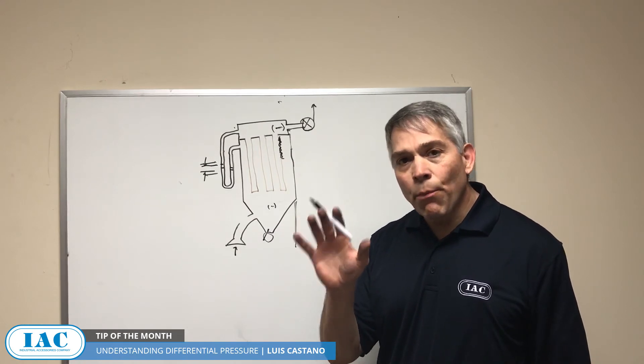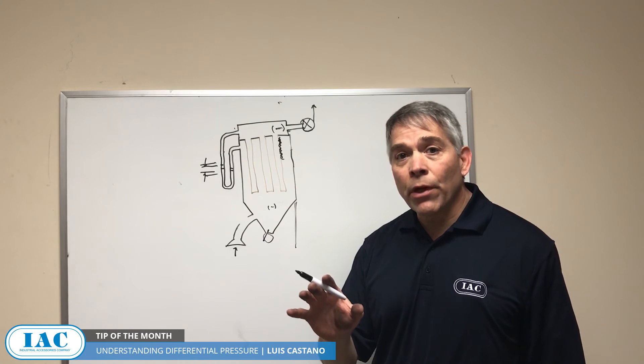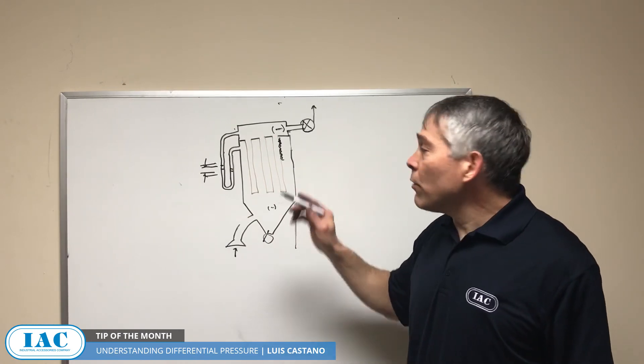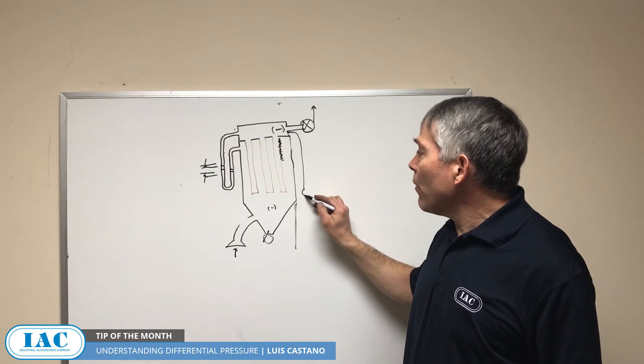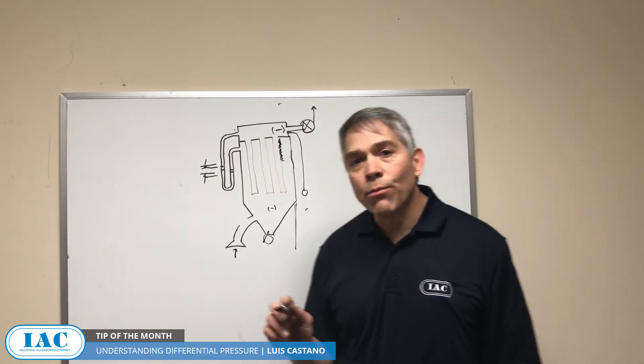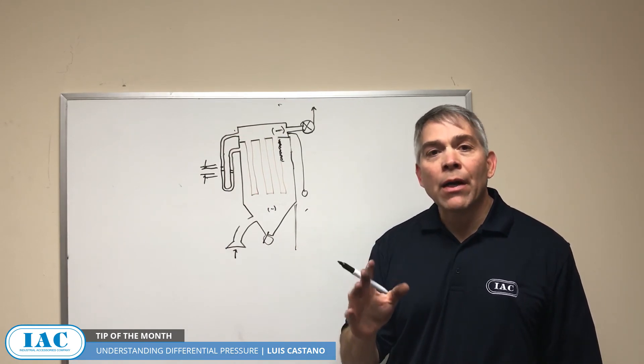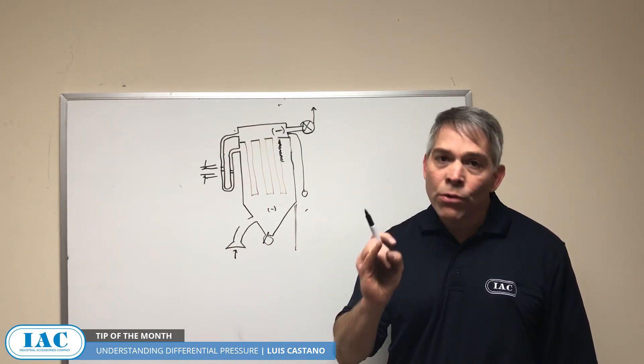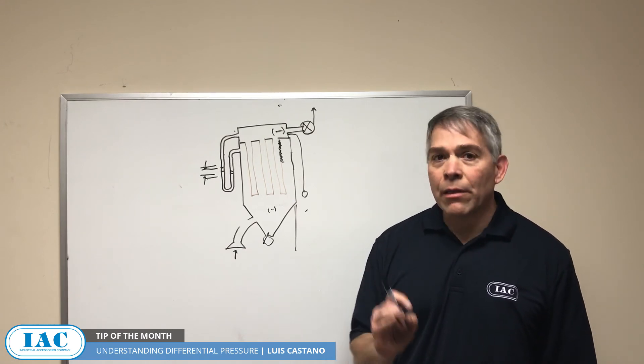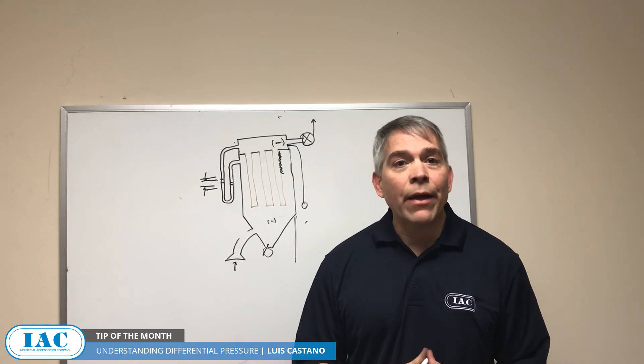So it's important to monitor differential pressure, it's important to keep a record of differential pressure, and if it jumps then you know there's an issue. It'd be good to have a differential pressure monitor somewhere where it's accessible and not way up on the bag house. Differential pressure — it's important to monitor it, have it accessible so it's done frequently.